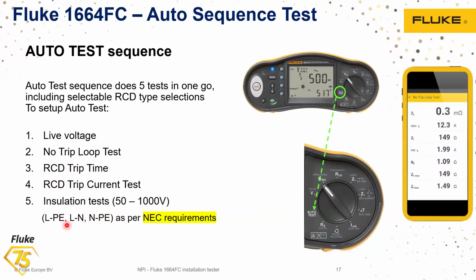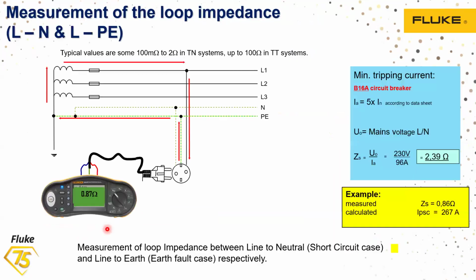Now, from the NEC requirement, what we need to understand is not only the fault impedance measurement. When you are doing the insulation test, it is recommended to do it between line to earth, line to neutral, as well as neutral to earth. Now, measuring the loop impedance: when we have a low resistance, the fault current can easily pass through. When there is a high resistance, it resists the flow of current, isn't it? So it's a basic Ohm's law principle.